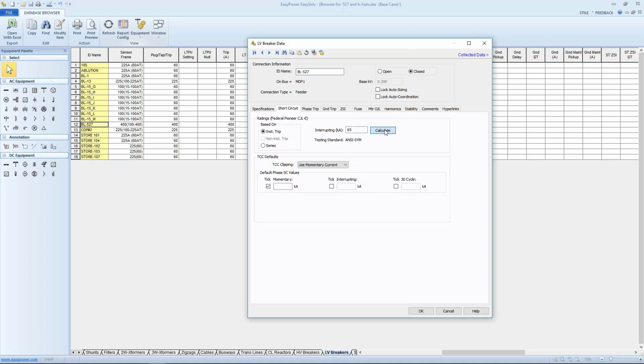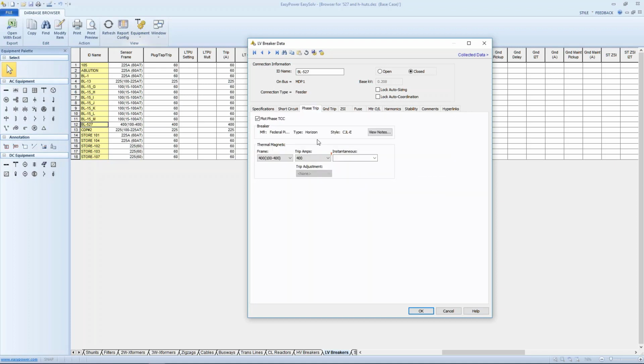As we go over here and look at the phase trip, we see, sure enough, he hasn't set up an instantaneous trip setting. Now, I think part of his response, and I'll come to this in a second, was, well, there was a label over the dial on the breaker, so I couldn't collect that data. Well, this is another case in point. What is it that you want to do? Do you want to analyze the system, or do you want to let a label stop you from updating what's actually being done?